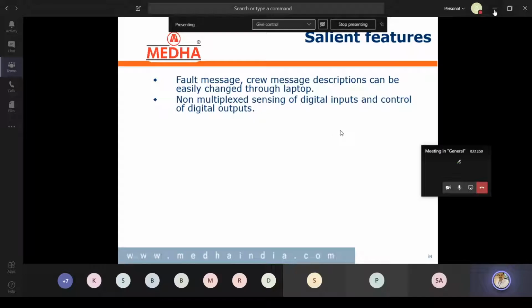And non-multiplexing sensing of digital inputs and control of digital outputs. In the earlier system there are MUX cards, so there were a lot of failures in MUX cards. In our case, it is non-multiplexing sensing of digital inputs. So there are no MUX cards, just direct one-to-one reading. Driver ID, train number, section name, etc. are set through the display keyboard. Using the display keyboard only, we can enter all this information.